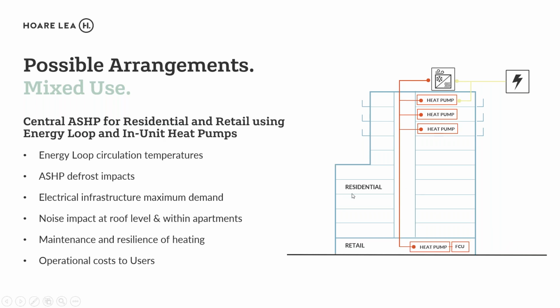So the alternative solution that a lot of clients are requesting, and that is reviewed in some detail, is looking at an energy loop, where you circulate lower temperature grade water and put in air source heat pumps or water source heat pumps to elevate temperatures into the space, which will do hot water generation and space heating at lower temperatures. Again, in most residentials, that space heating is actually very low in demand, and so we're looking at hot water generation. You still have issues with electrical infrastructure, but you then have the options for the calculations on diversity, probably more so than the electrical top-up, because the electrical top-up on apartments on the previous slide was probably less in diversity than this arrangement.